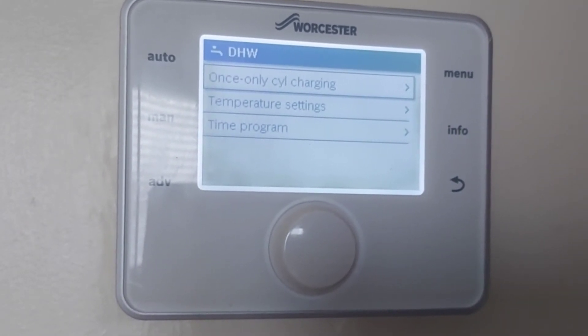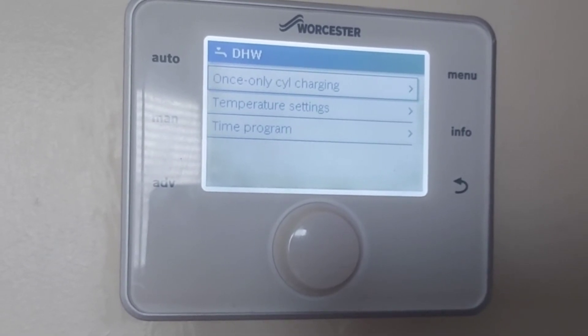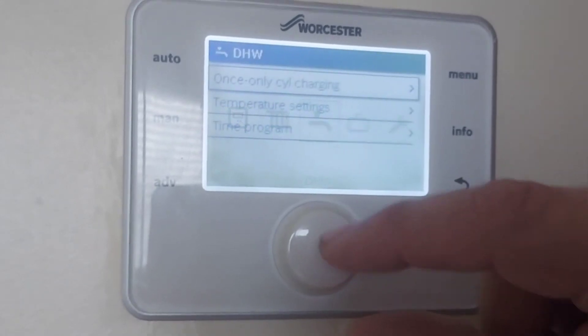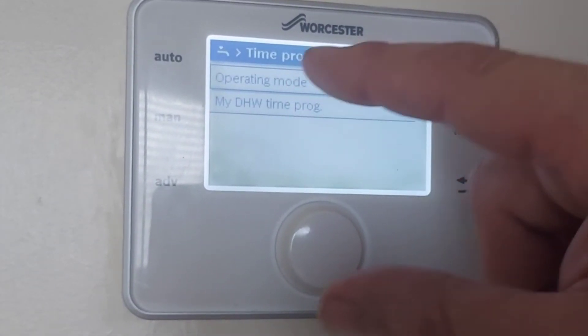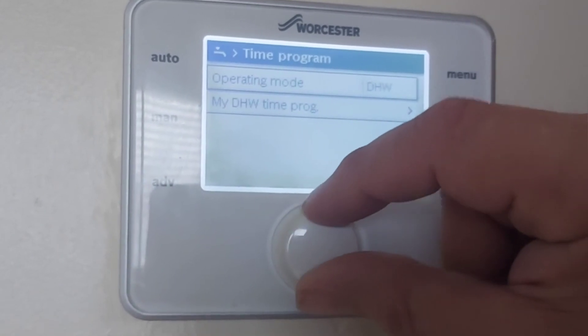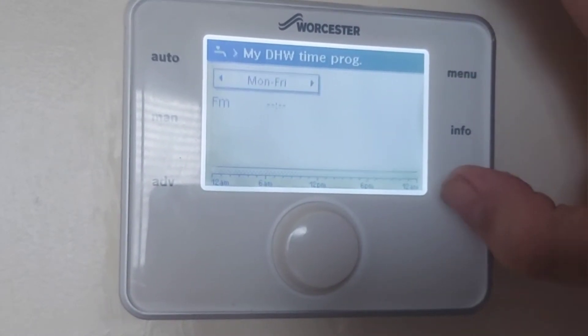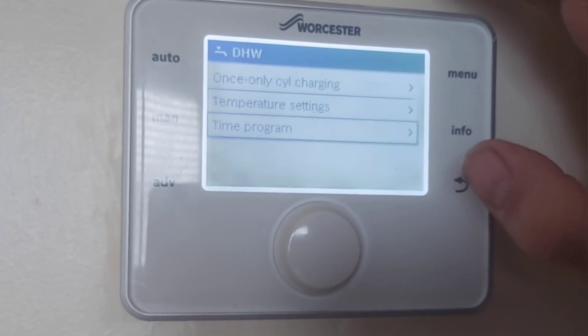For hot water you can set it to heat up once a day, with temperature settings and a program. You can set it to heat up two, three, or four times a day. Go in here, press that, scroll down to time program, then operating mode for domestic hot water, and set your times. But if it's a combi, just set it to constant — it only makes hot water when you turn the tap on.